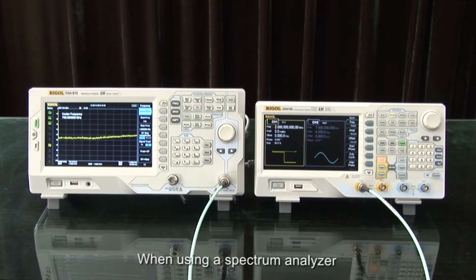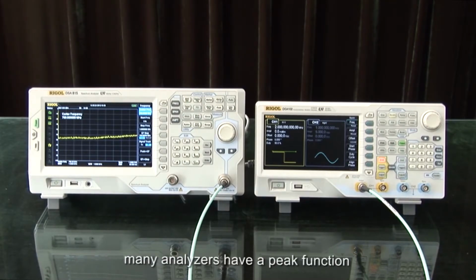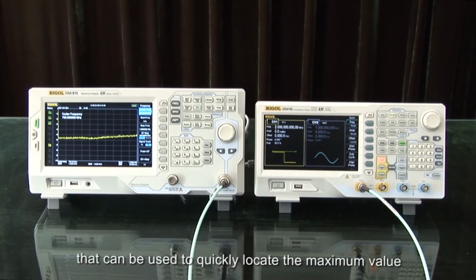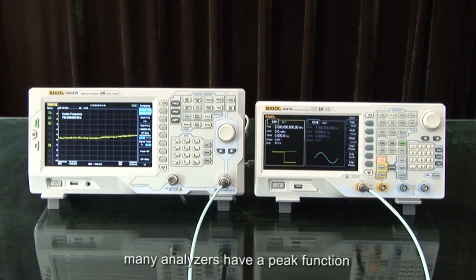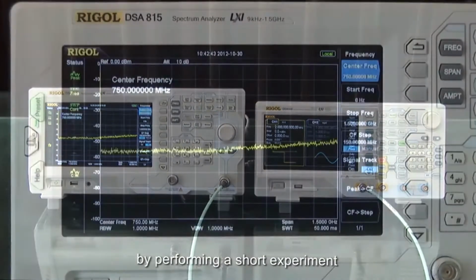When using a spectrum analyzer, it's very common to measure the maximum amplitude of the signal spectrum. To make this measurement more convenient, many analyzers have a peak function that can be used to quickly locate the maximum values. Let's take a closer look at the peak function by performing a short experiment.